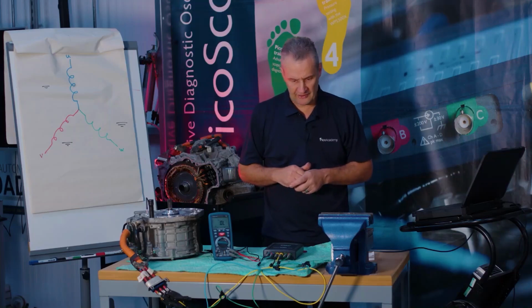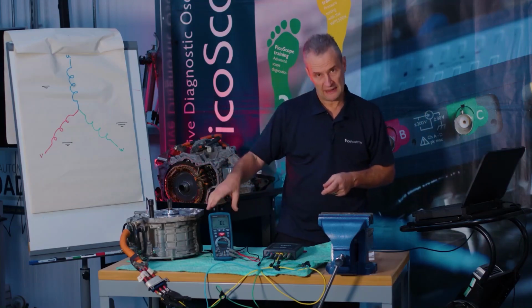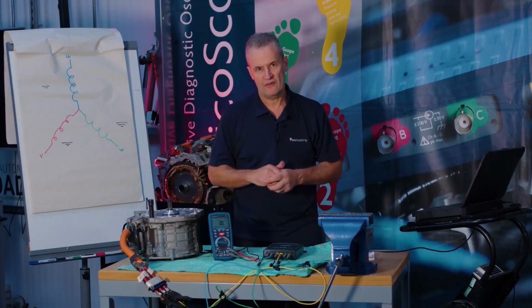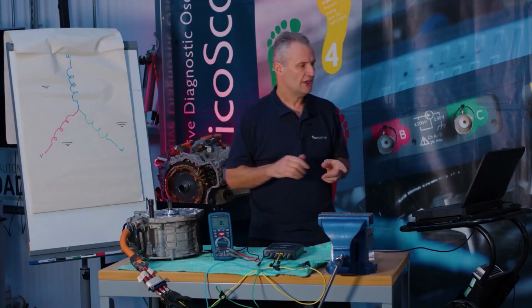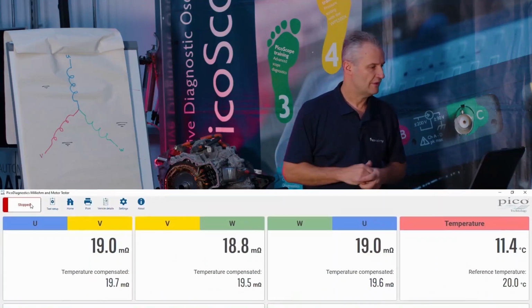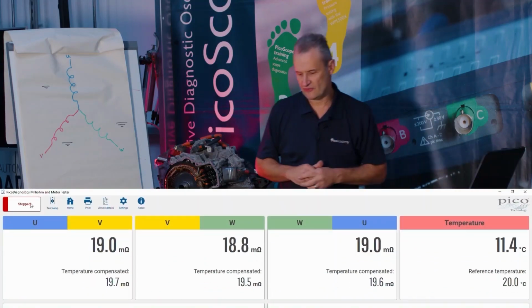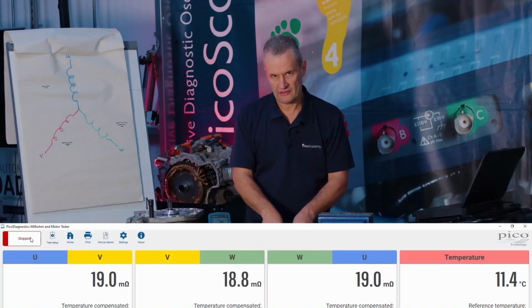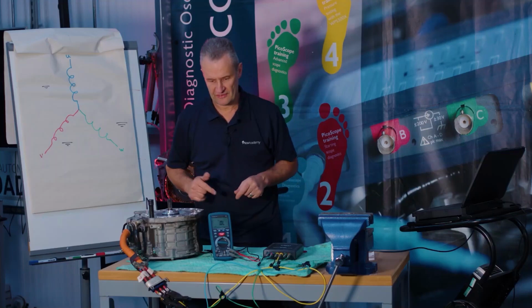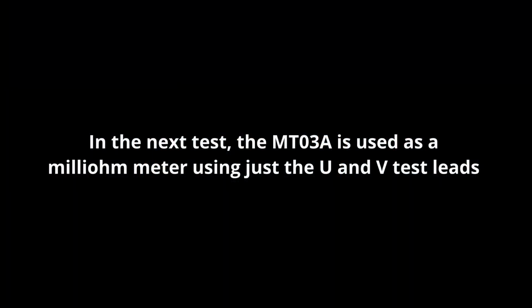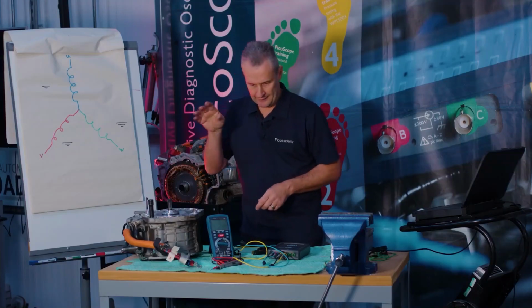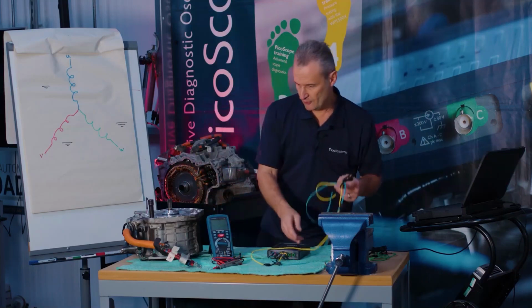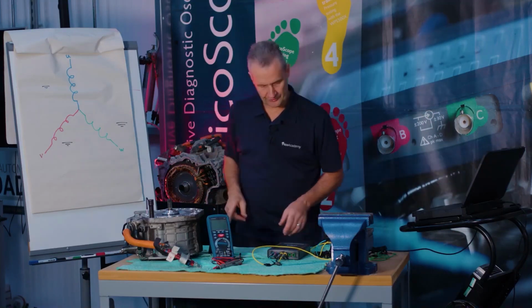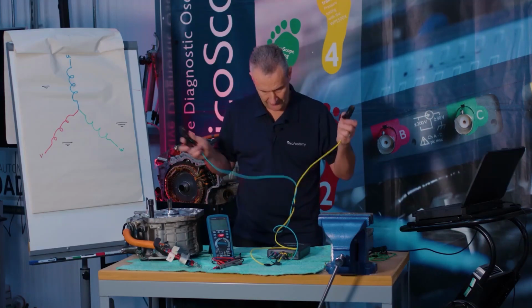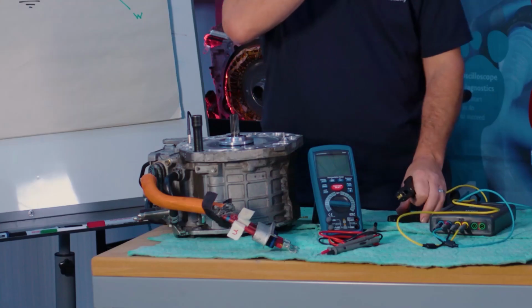Notice there, we did, I guess you could argue, have balance with this, but this read approximately 50 milliohm per phase. The actual true reading using this four wire method was 19, give or take. So far more accurate using the milliohm meter with far better resolution. Okay, so coming back to this motor, we do have a problem. The balance of the phases was good. What I'd like you to look at now is the resistance to ground.